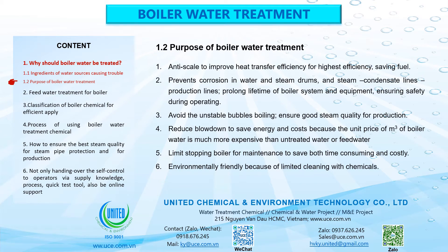1.2 Purpose of Boiler Water Treatment. 1. Anti-scale to improve heat transfer efficiency for highest efficiency, saving fuel. 2. Prevents corrosion in water and steam drums, steam condensate lines, and production lines; prolong the lifetime of the boiler system and equipment, ensuring safety during operation. 3. Avoid unstable bubble boiling; ensure good steam quality for production. 4. Reduce blowdown to save energy and costs, since the unit price of boiler water is much more expensive than untreated or feed water. 5. Limit boiler stoppages for maintenance to save both time and costs. 6. Environmentally friendly because of limited cleaning with chemicals.